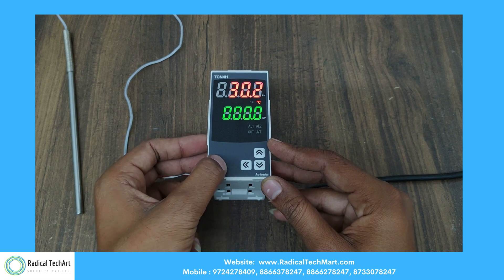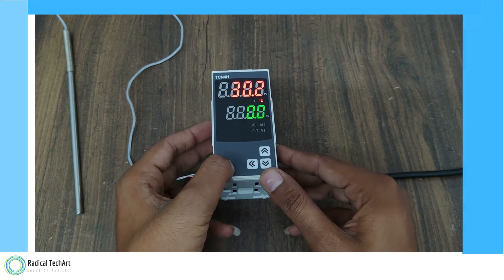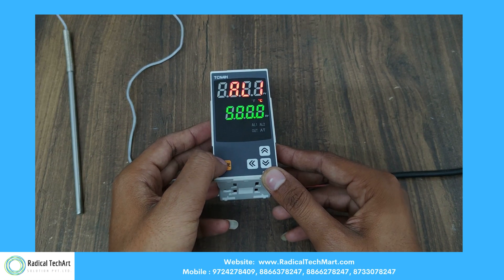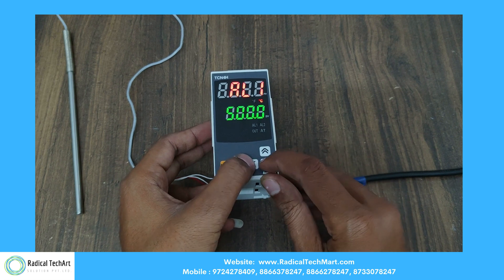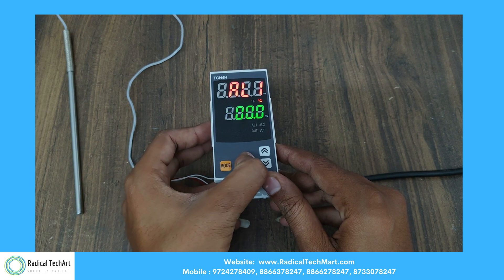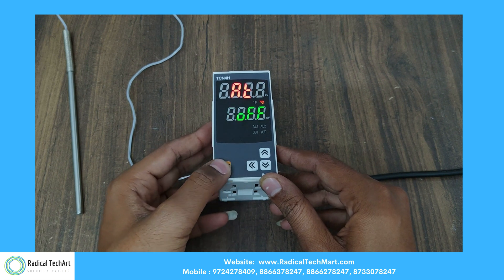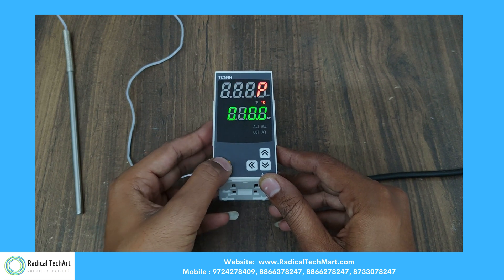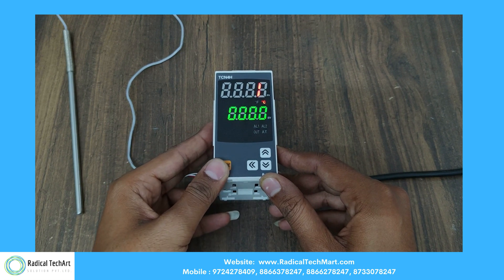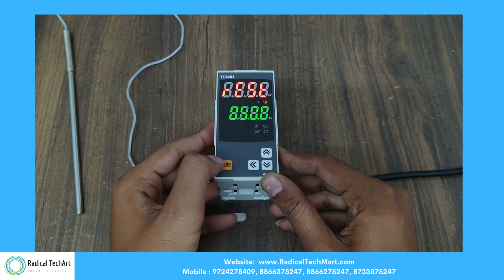First, we have the mode option on the left-side bottom where we can set a value. After that, we press the mode button for 3 seconds. AL1 is for alarm temperature. AL2 is also for alarm temperature. AT is for auto-tuning. P is for proportional band. I is for integral time. D is for derivation time. Reset is for manual reset.